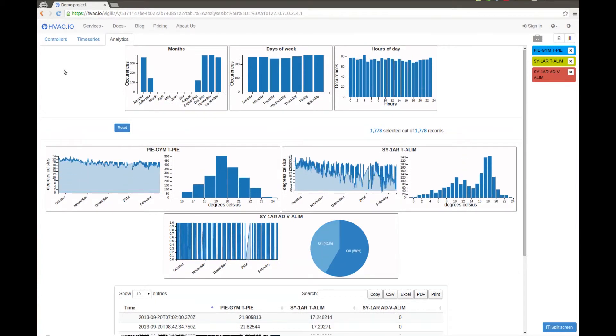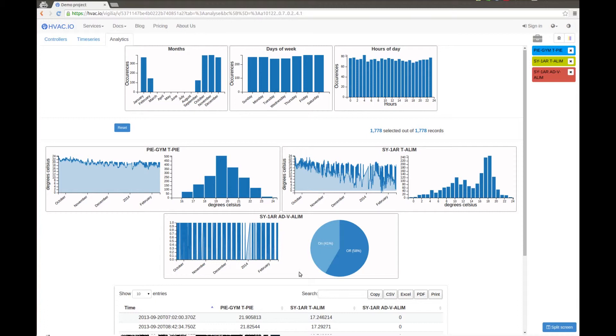Let's say that we just stumble upon this system. We want to understand how it works. So the first object here is the room temperature, this is the air supply, and this is the fan operation. So the room temperature, this is the temperature profile, a normal curve centered around 19 to 20 degrees, which for a physical education room is understandable.